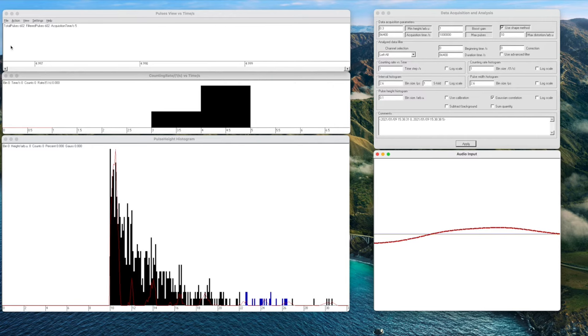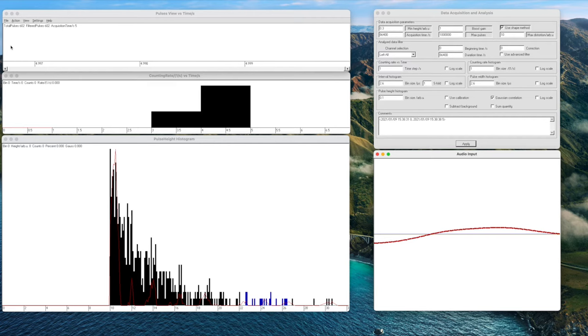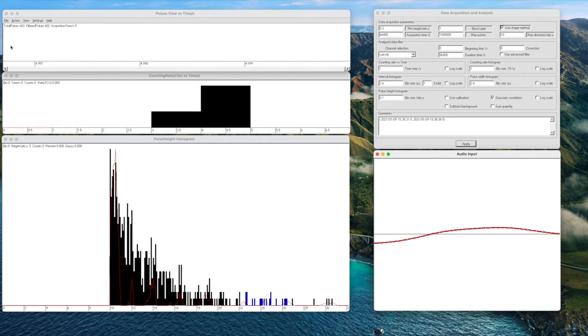The first thing we are going to do is teach the software what the pulse shape from our detector looks like. In order for PRA to do pulse shape discrimination it needs to know how a good pulse shape looks. Each detector and each spectrometer might have a slightly different pulse shape so it's important that we teach the software how it looks before we start and we do that by doing the pulse shape acquisition.